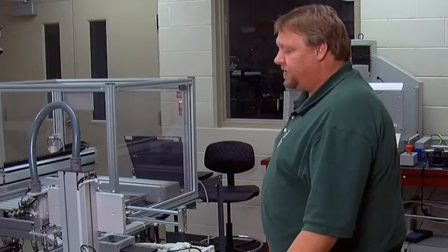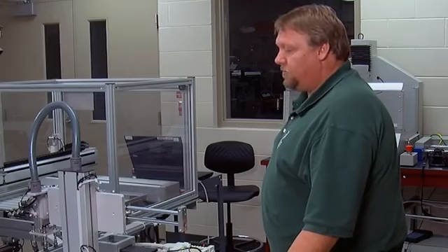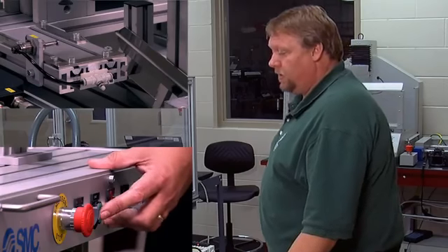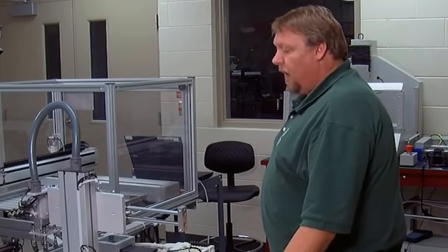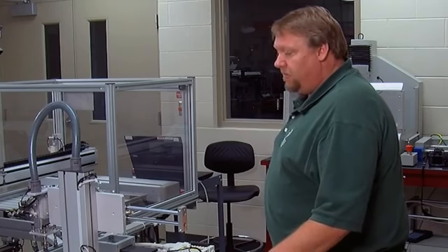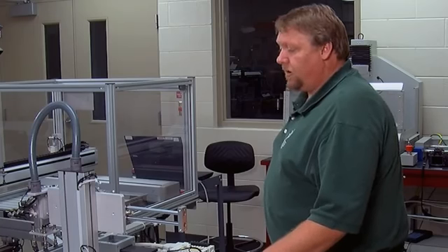Step 5 is extend the pusher cylinder. Step 6 is retract the pusher cylinder. Step 7 is reject the body. Step 8 is to retract the rejection cylinder. And then step 9 finally completes the reject cycle complete. So now that we have the reject cycle complete, we know all the series of events and the steps it's going to be required to program it. We can add those to our Excel file.